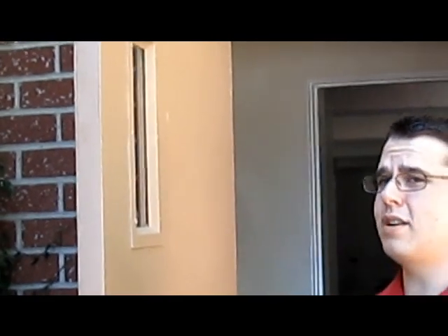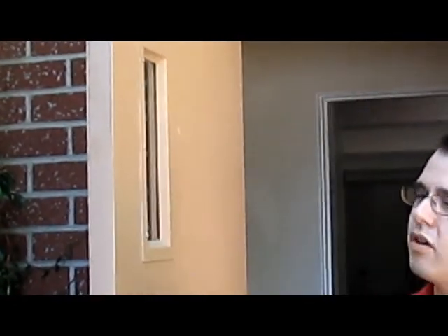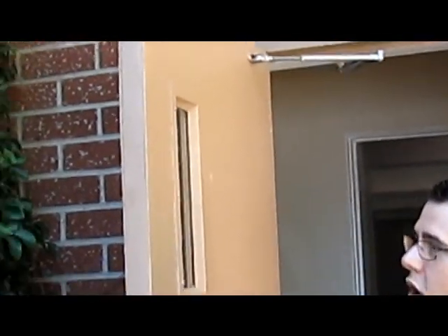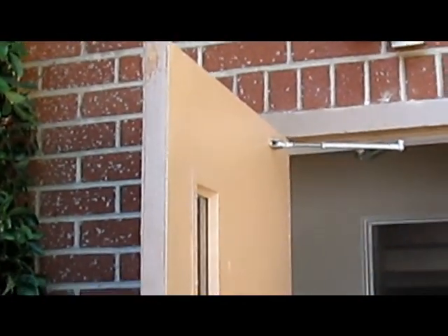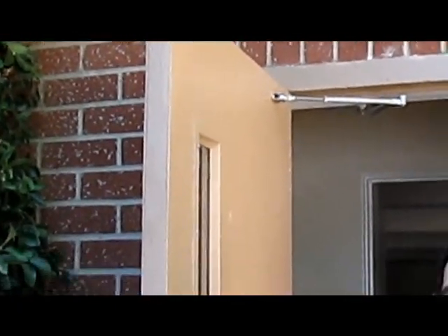Sadly, in my opinion, at one point this heavy-duty door was a fire-rated door with its fire-rated glass and all, but at one point the label must have been removed or painted over. Thus, if the label has been removed or permanently covered, it voids it being considered a fire-rated door.